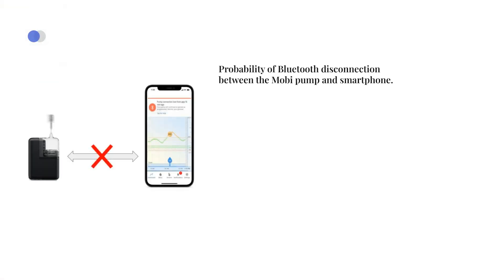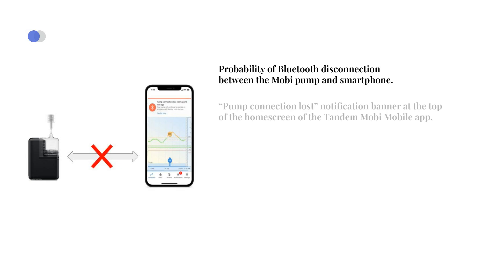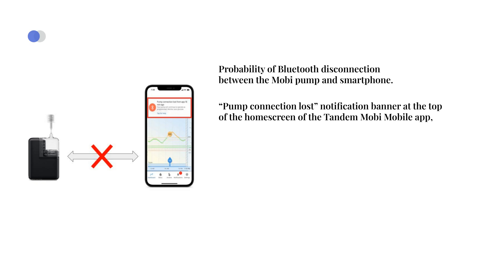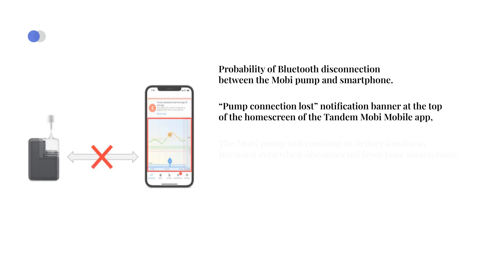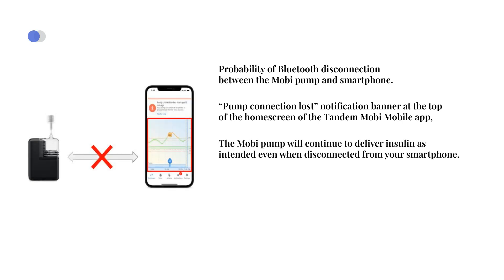It's also possible that there is a Bluetooth disconnection between the Mobi pump and your smartphone. In that case, you will see a pump connection lost notification banner at the top of the home screen of the Tandem Mobi mobile app, together with how much time has lapsed since your pump disconnected from your smartphone. You will also see a gray shaded area on the graph since no data can be displayed when the connection is lost. The Mobi pump will continue to deliver insulin as intended, receive glucose values if paired to a CGM, and all pump alerts, alarms, reminders, and malfunctions will enunciate on your pump, even when disconnected from your smartphone.